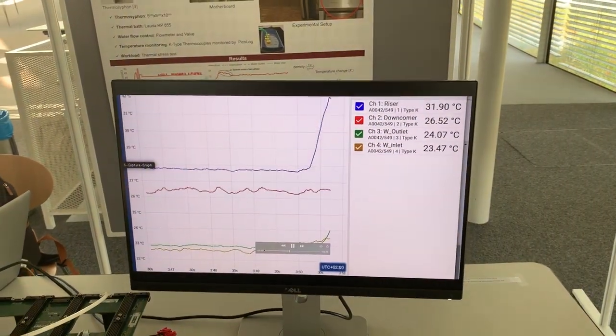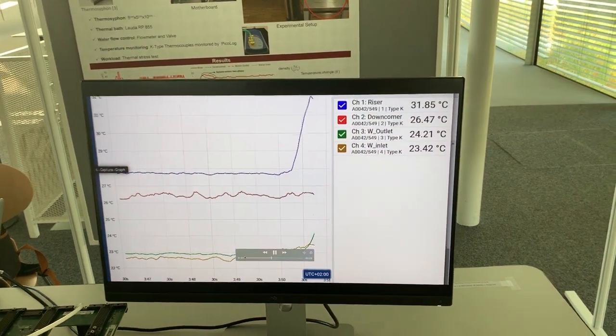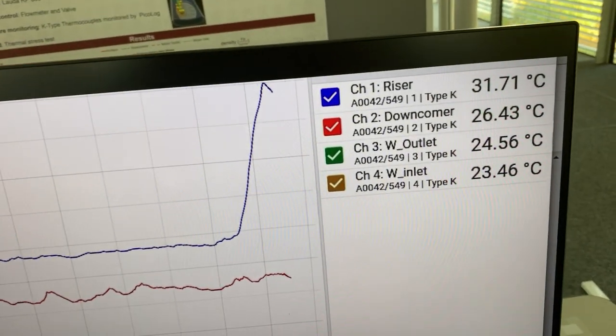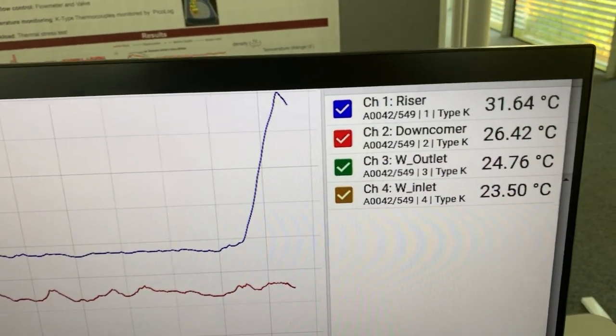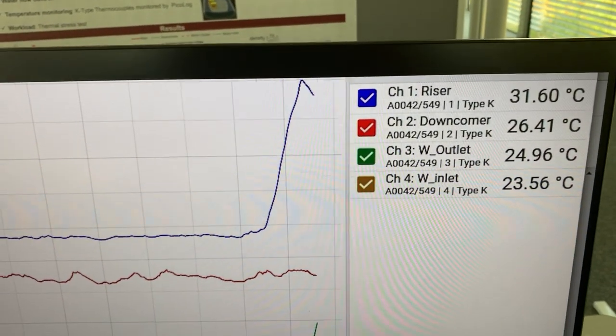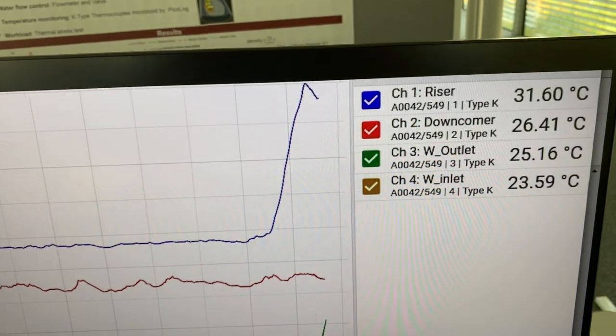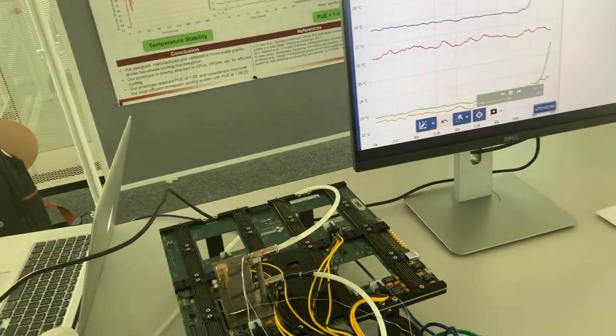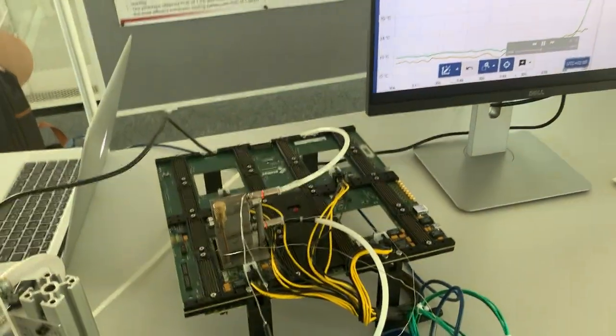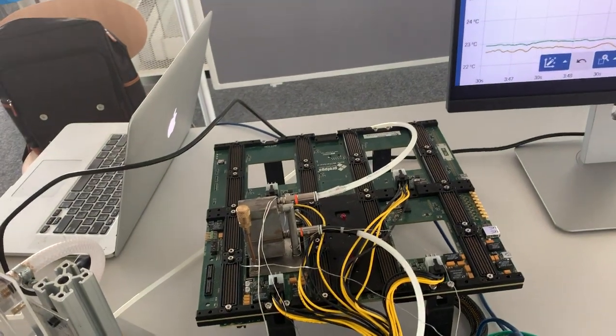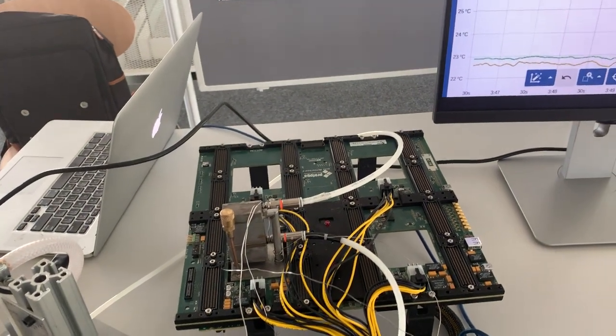Exactly here. So you see that the temperature is going down because it's when the two phase has started. So when the two phase starts, the temperature of the chip is under control.